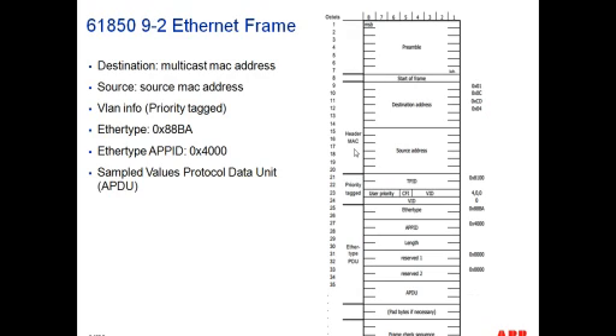Based on our real experience in projects that we've deployed worldwide, you really would want a bandwidth allocation of about 4 to 5 megabits per second per IED. Given that the prescribed media for these types of installations is 100 megabit Ethernet, you can do the math on how many devices you can have inside an unsegmented network. By unsegmented, I mean one that does not support virtual LANs.